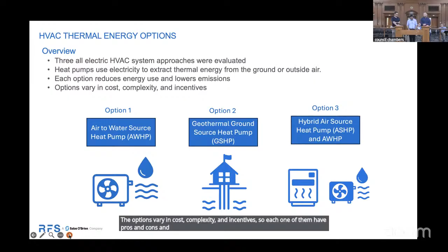Next slide is option one, air-to-water source heat pump. Like I described earlier, in this particular option, the air-to-water source heat pumps are going to be located inside the well and are going to be used to provide heating and cooling. They have an inherent limitation where they stop operating at certain ambient conditions, so they require a backup source, which would be boilers. The boilers will only be used as a backup when the temperatures go sub-zero.